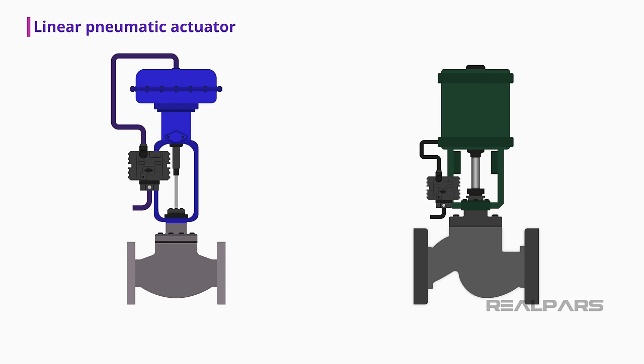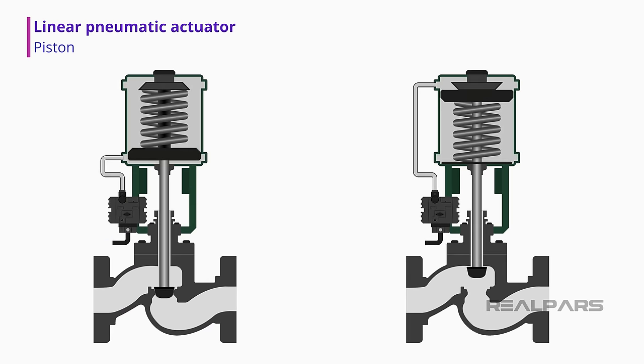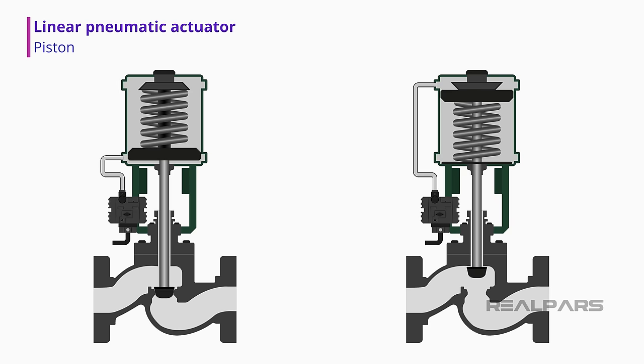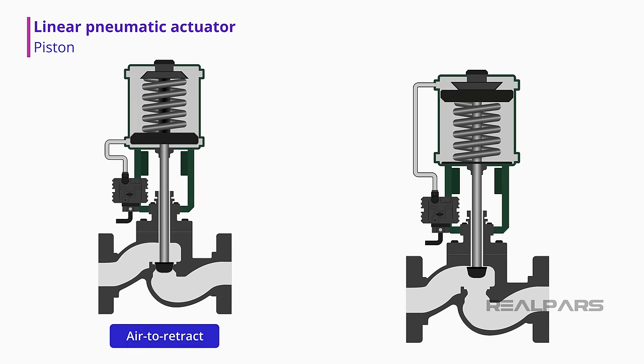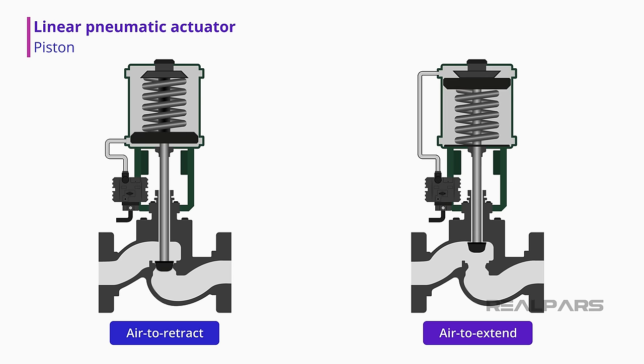In the linear pneumatic actuator category, the spring diaphragm style and the piston style are very common. The piston style pneumatic actuator utilizes a piston inside a cylinder. The movement of the piston is caused by applying pneumatic pressure, thereby moving the piston upwards. Removing the pneumatic pressure causes the piston to move downward due to the pressure of the spring — this motion is referred to as air to retract. An air to extend motion can also be achieved by rearranging the spring, piston, and pneumatic supply.